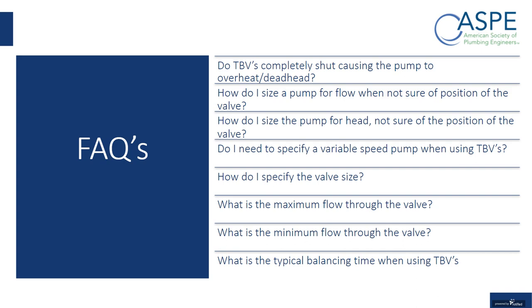Do I need to specify a variable speed pump when using thermostatic balancing valves? That's a big question I get a lot, and that is no, you don't, because 10 years ago, 97% of the applications had no adjustable variable speed pumps in there. Now today, that's a lot higher, but still, I would say out in the field, probably 80 to 85% at least of the installations are all fixed speed pumps.